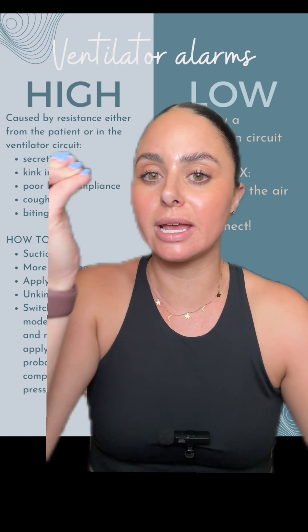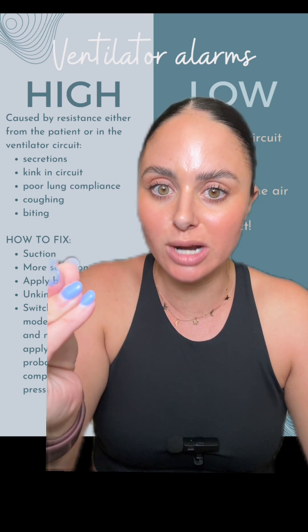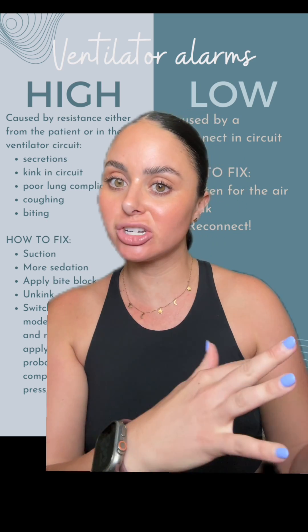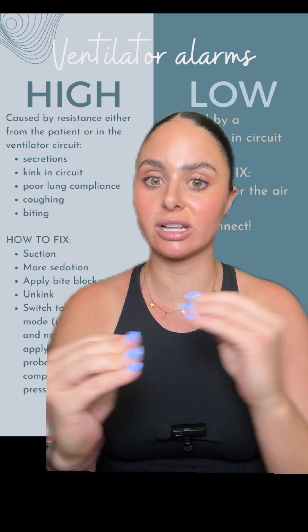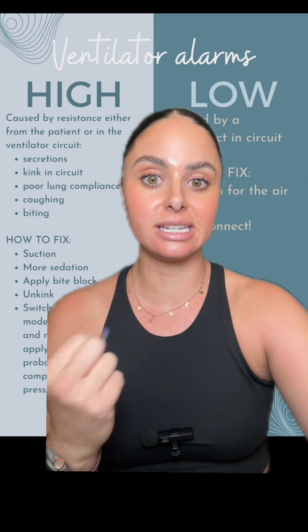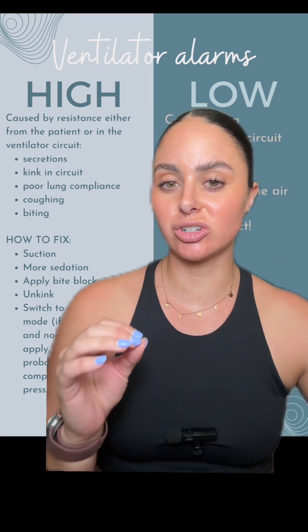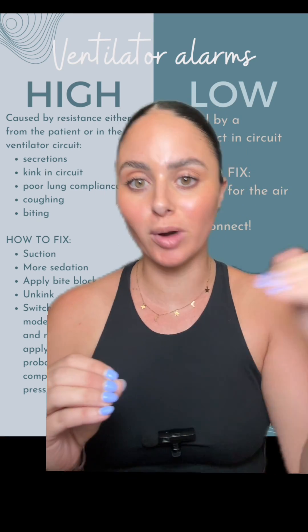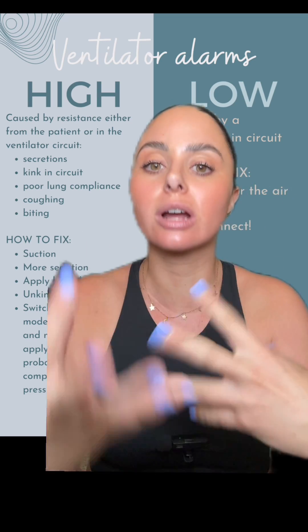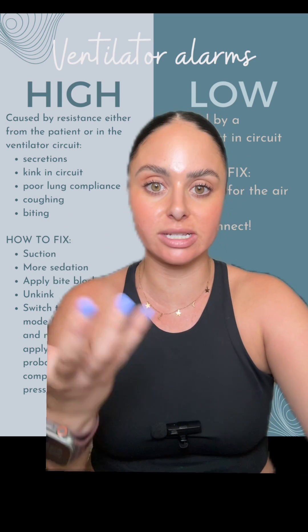For your high pressure alarms, these alarms will say something like high pressure, peak airway pressure, or maximum pressure. These types of alarms are caused by resistance either from the patient or somewhere in the ventilator circuit — whether that's the ventilator tubing or the patient's ET tube. Anything that causes the ventilator to push more pressure into the circuit to overcome resistance is going to trigger these alarms.